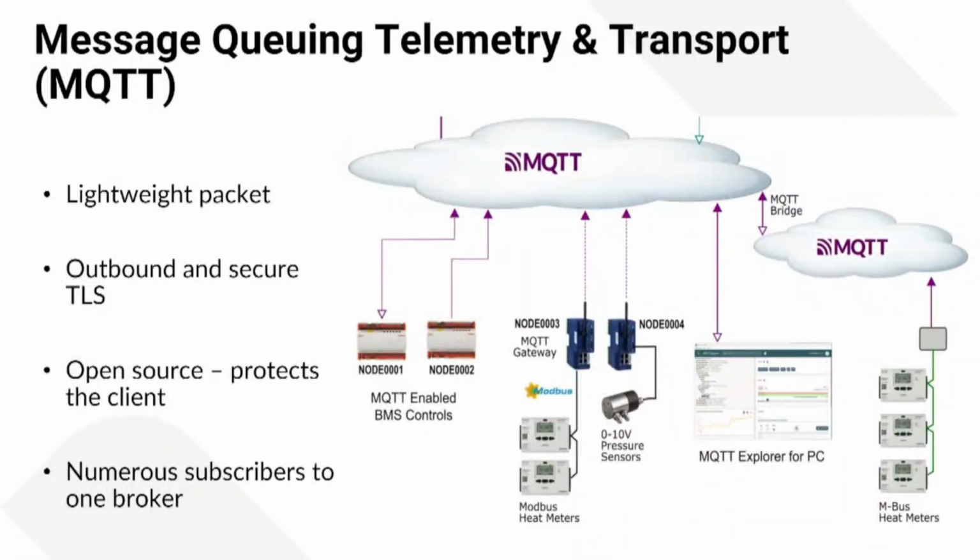Just to clarify, to enable a BMS to export or publish MQTT may require specific licensed software. Once the data is in the MQTT protocol, that is when open source software can be used. The MQTT data is sent and held in the cloud and is called a broker.